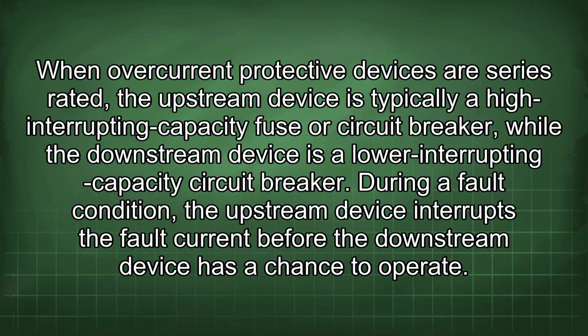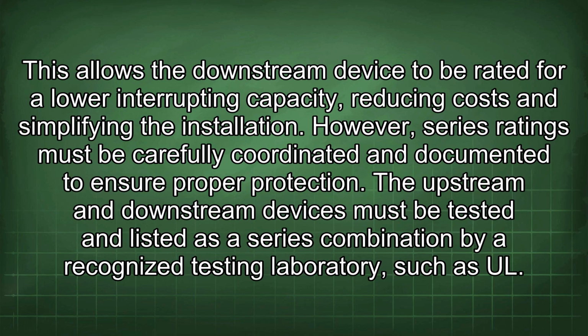During a fault condition, the upstream device interrupts the fault current before the downstream device has a chance to operate. This allows the downstream device to be rated for a lower interrupting capacity, reducing costs and simplifying the installation. However, series ratings must be carefully coordinated and documented to ensure proper protection.